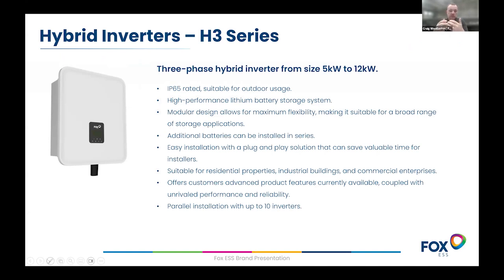This one has an AC variant called the AC3, but you can AC couple with the H3 as well without any fuss. It's an IP65 inverter, and connects back to a meter which is always supplied with the product. We supply a Chint DTSU 666, and it comes with a CT, so you connect that back to the incoming supply. You can parallel these inverters too, for system scalability, all of our inverters can be paralleled just using data cables to link them together in a daisy chain to expand the system.